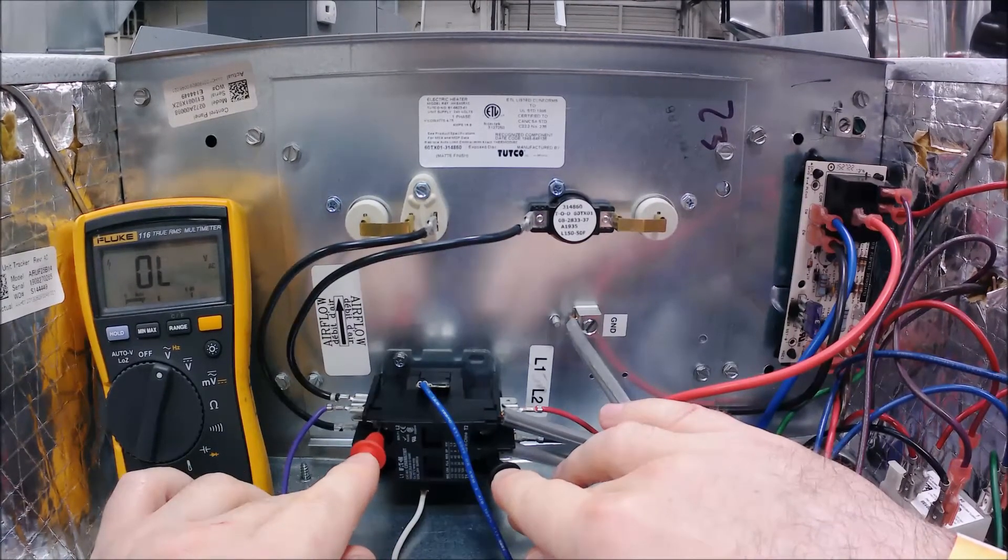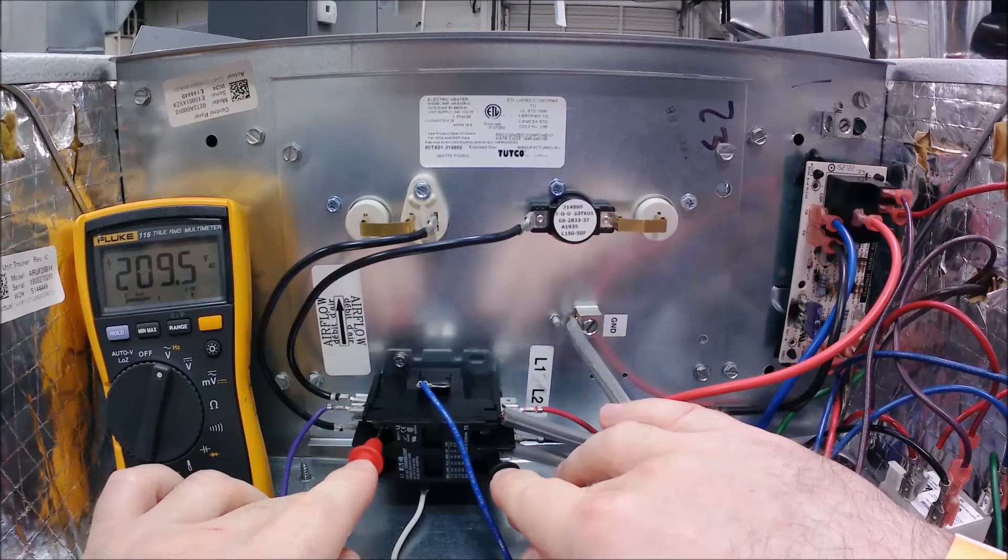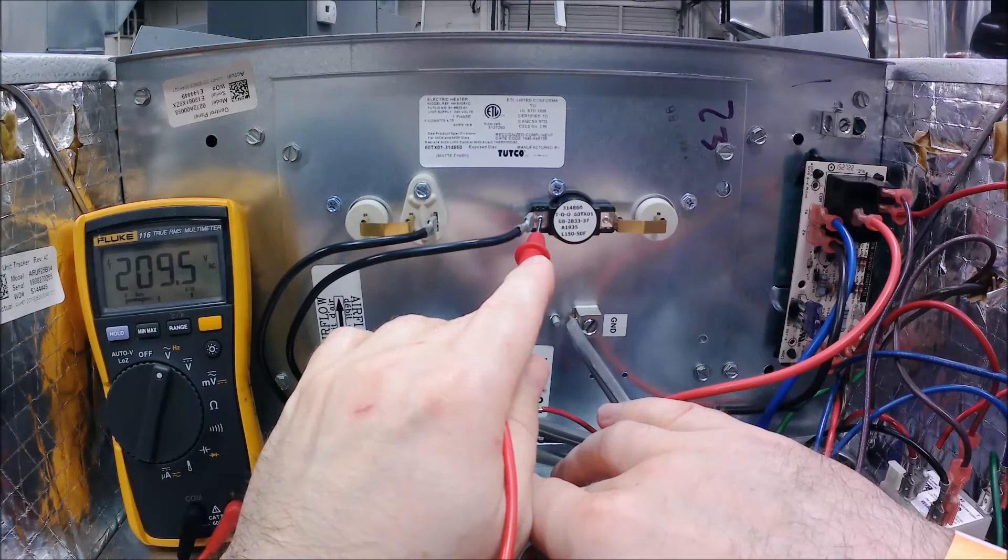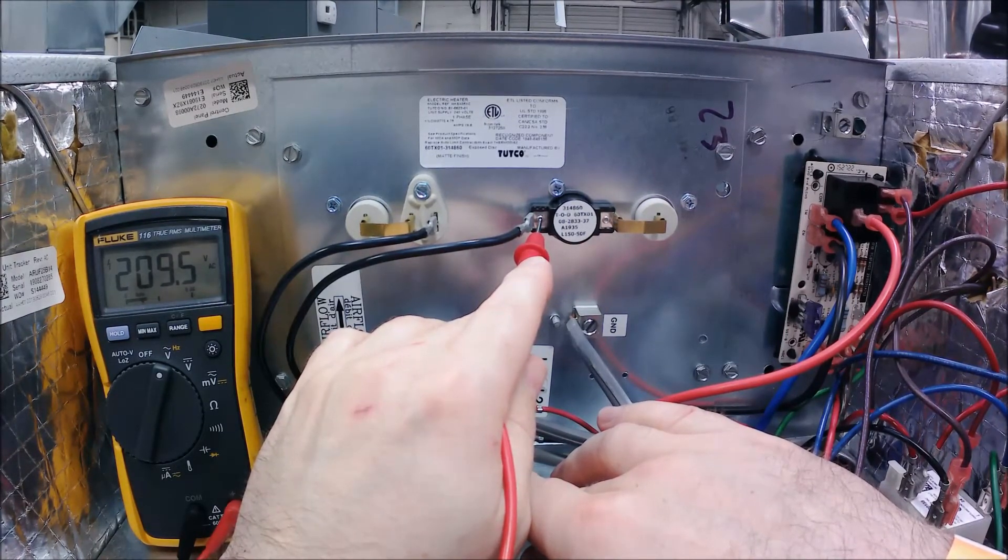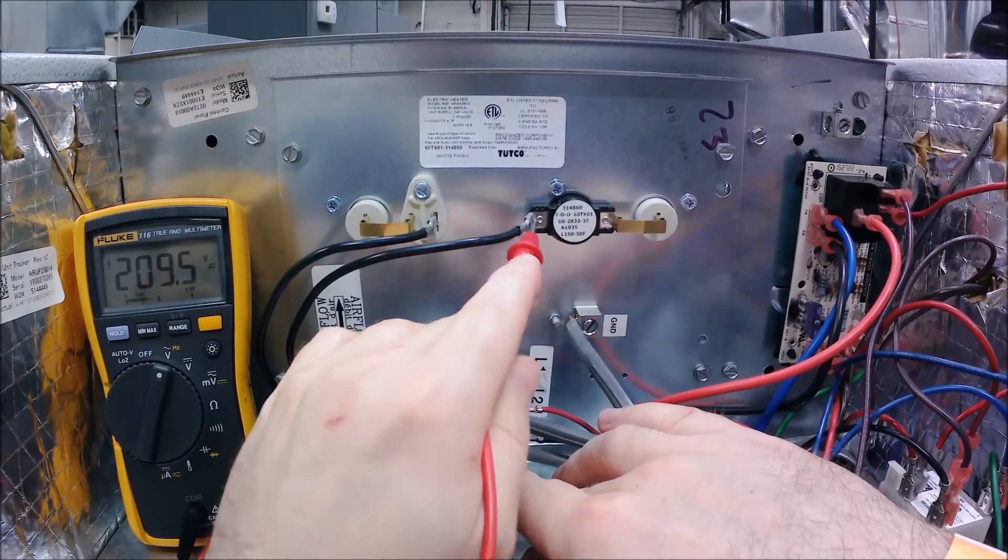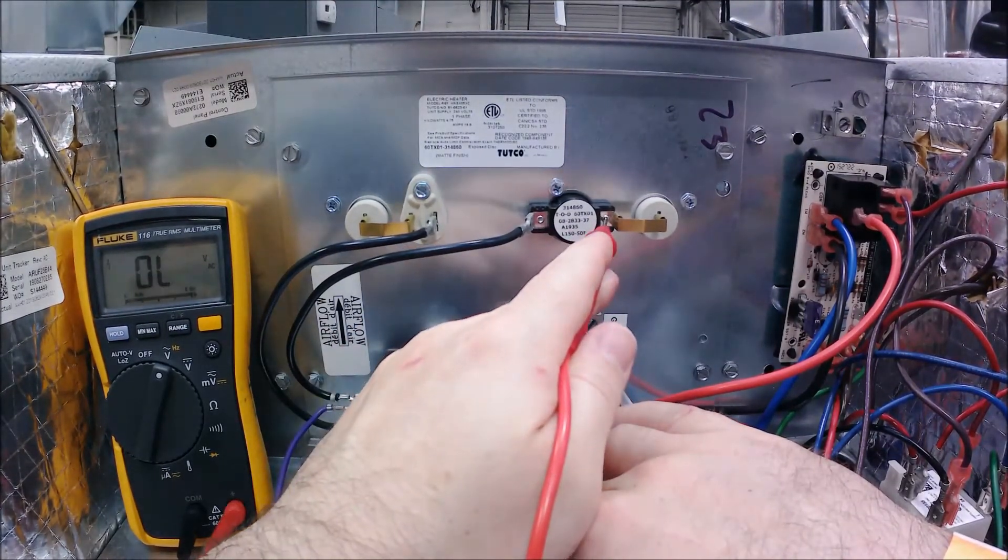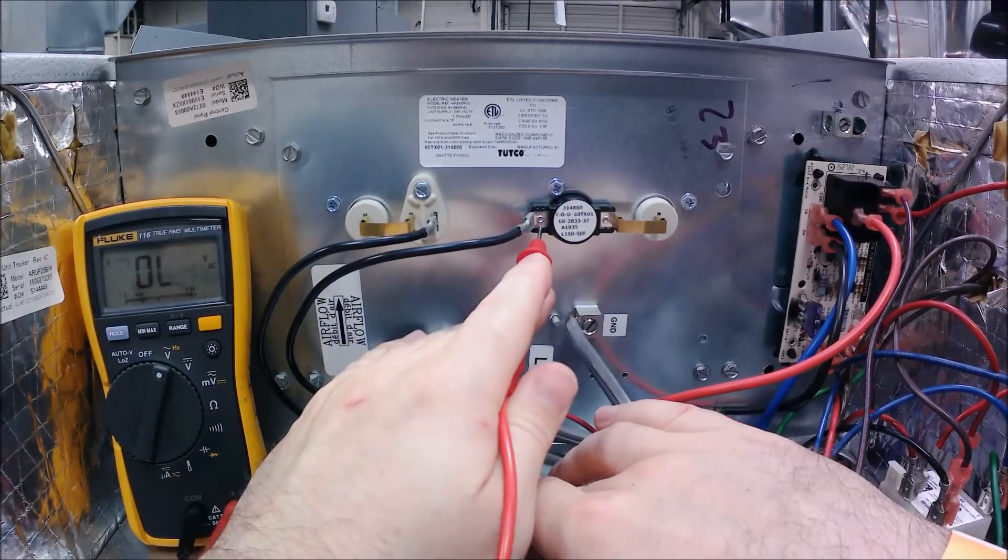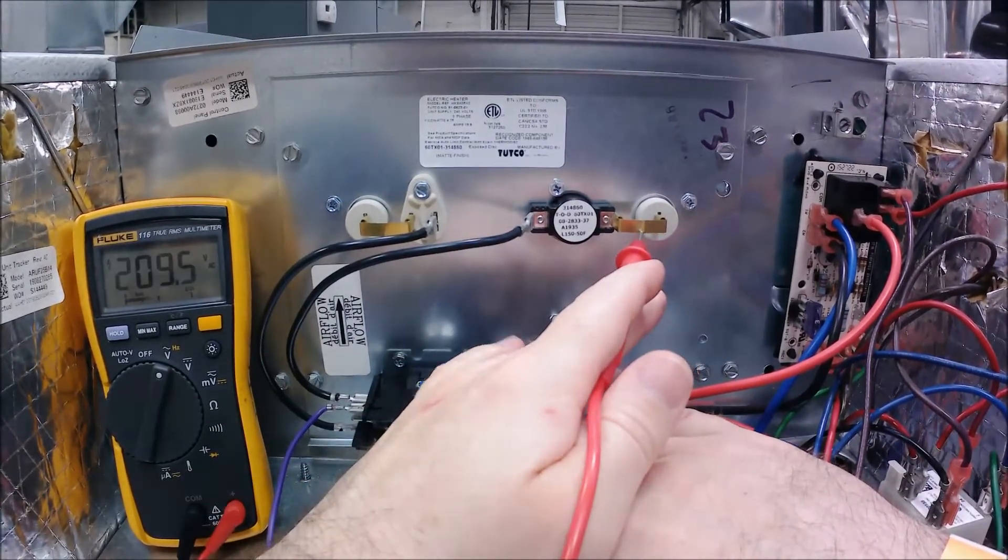So with the hopscotch method you simply follow the circuit. I could go from here at the contactor and I can go into my first safety, my high temperature limit. I've got 210 volts going in, and if that safety was the problem I would have zero coming out, but I've got 210. So I've got power going in the switch, power coming out of the switch.